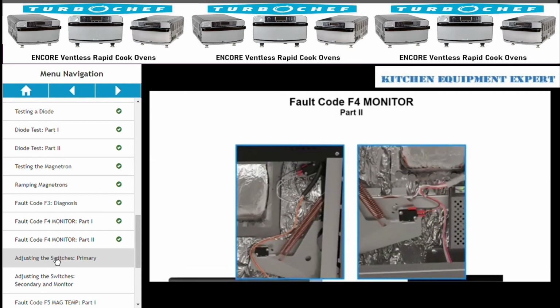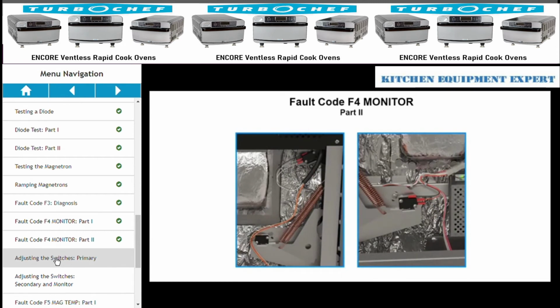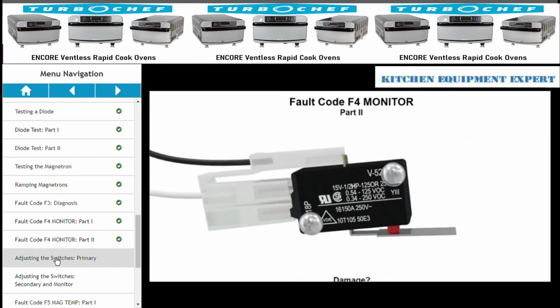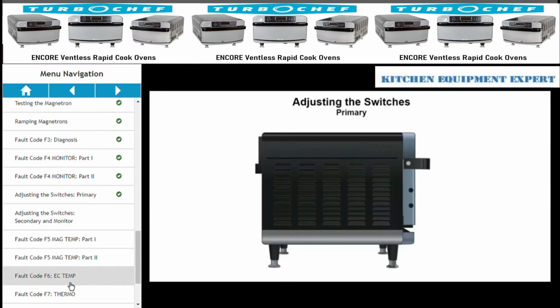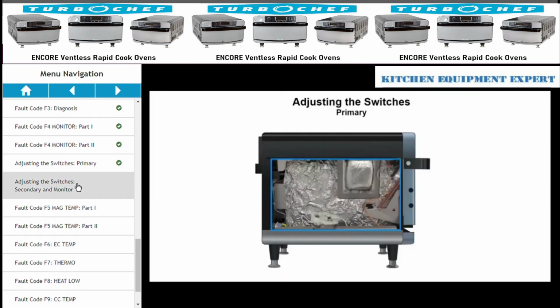If the switches are not opening or closing in order, they need to be adjusted or replaced. Look for signs of physical damage, such as a bent actuator tab or signs of arcing. If a switch is damaged, it must be replaced. One or more of the switches just may need to be adjusted.